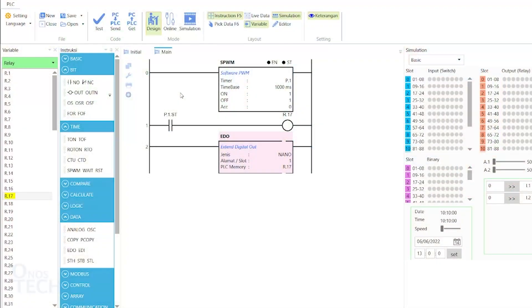The EDI will read the 8 digital inputs, S.1 to S.8 of the extended IO module and assign their values to variables S.17 to S.24. It will also read the 2 analog inputs, A.1 and A.2 and assign their values to A.3 and A.4.